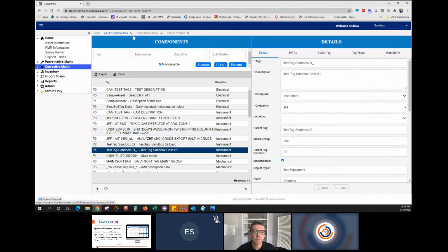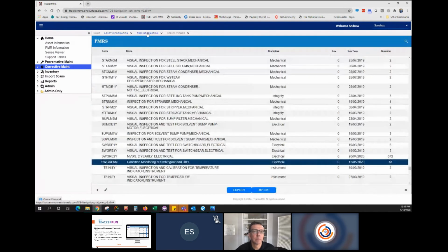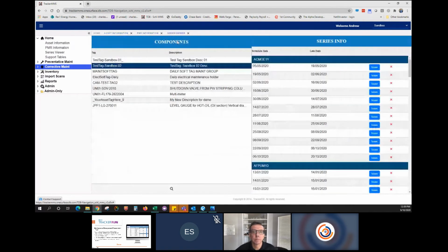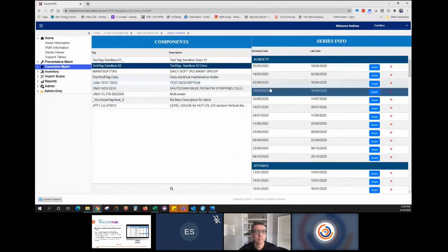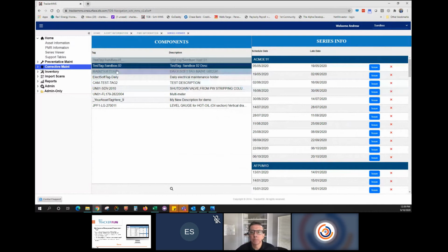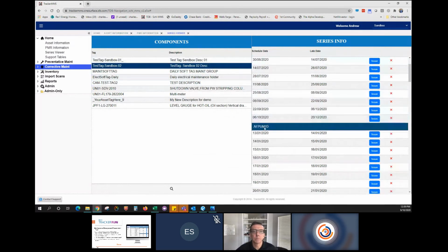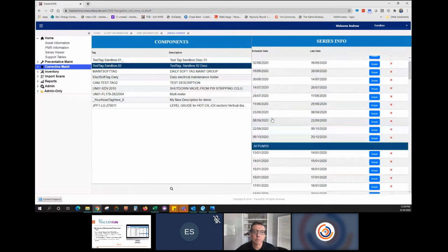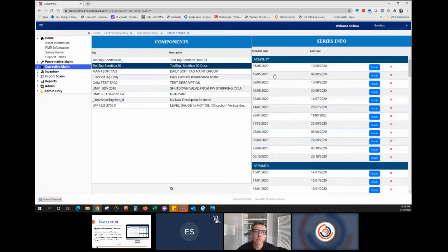So we've brought in tags, brought in the PMRs for the tags, and tied them together. Once tied together, they show up in the series viewer. Here are my tags on the left side, and here are all the PMRs required in dark blue, with the periodicity of when they're due. The system automatically generates a full year's worth of maintenance when you assign a PMR to a tag and give it a start, unless you give it an end date.